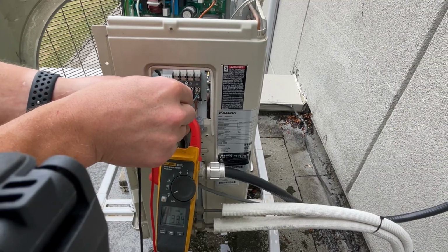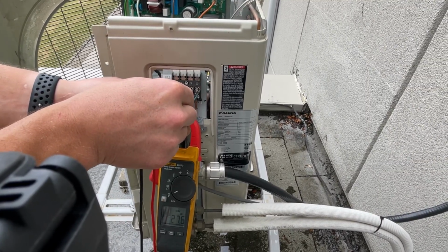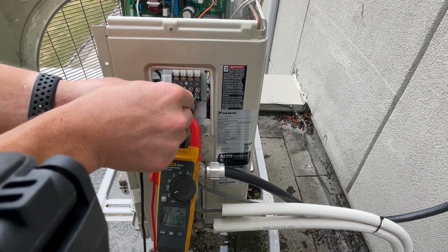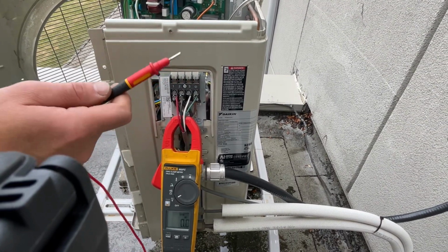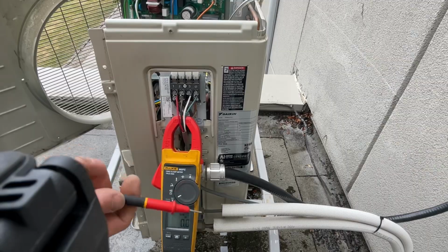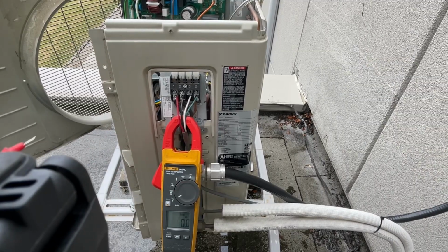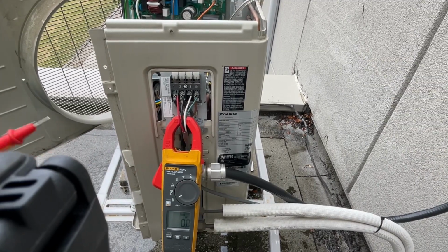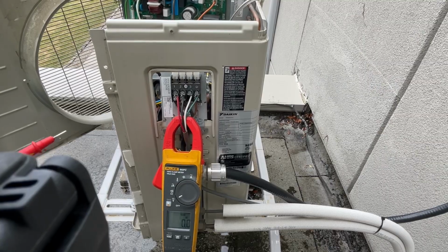So this board is not putting a proper signal out, guys. This board is also finished off. That condenser fan motor took this board out, and yeah, we're going to have to change our main board and our condenser fan motor. We verified that our electronic expansion valve is fine and our compressor. We'll go talk to the customer now and see what they say.